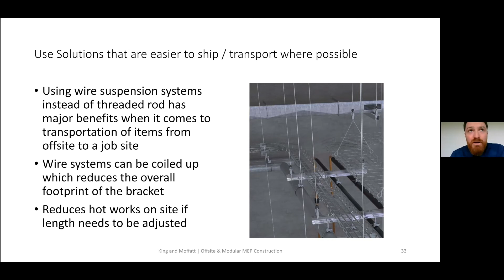Now, for ELV baskets and cable trays, you probably wouldn't want to be running your submains cable ladders on them for weight reasons and for pulling cables along afterwards - there'd be too much sway. But for other areas with huge runs of fire alarm, ELV, and LV cables, there's no issue.